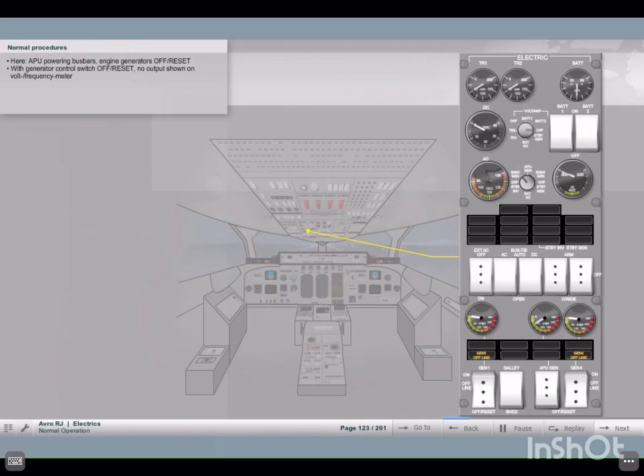Both engine generator control switches are set at off reset. This is to clear any faults detected by the GCUs and to de-energize the generator excitation. Note that at this switch position, no output indication on the voltage and frequency meters is available. Function of the generator control switch offline position is to check the output of the generator output. Bring generator 1 to offline. Do it, please.